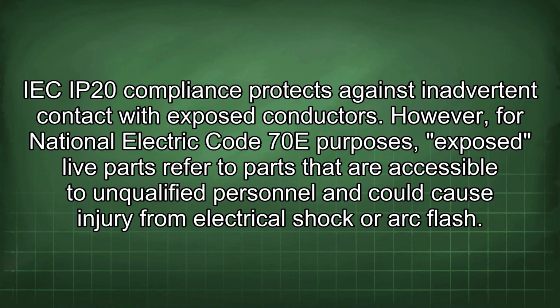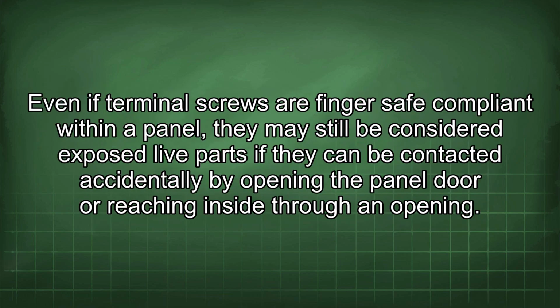IP20 compliance protects against inadvertent contact with exposed conductors. However, for National Electric Code 70E purposes, exposed live parts refer to parts that are accessible to unqualified personnel and could cause injury from electrical shock or arc flash. Even if terminal screws are finger safe compliant within a panel, they may still be considered exposed live parts if they can be contacted accidentally by opening the panel door or reaching inside through an opening.